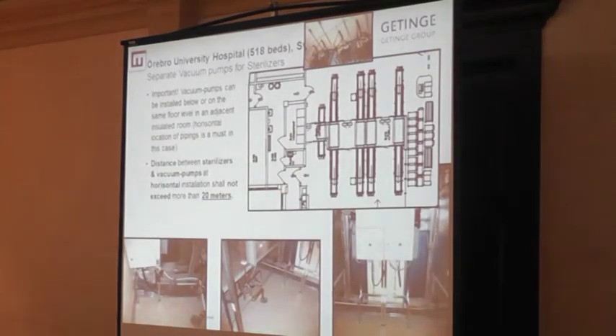So this is how it looked, the installation of the CSSD here. Electric cabinets, and the vacuum pumps. They can be moved out, but must be on the same floor level, in an adjacent insulated room nearby. Here are the vacuum pumps, shown in top view. So next to the sterilizer we have this room functionality.